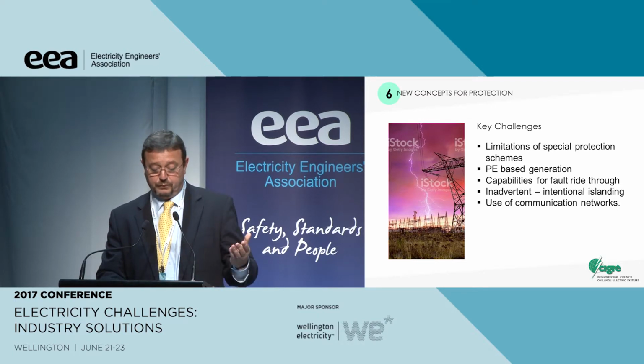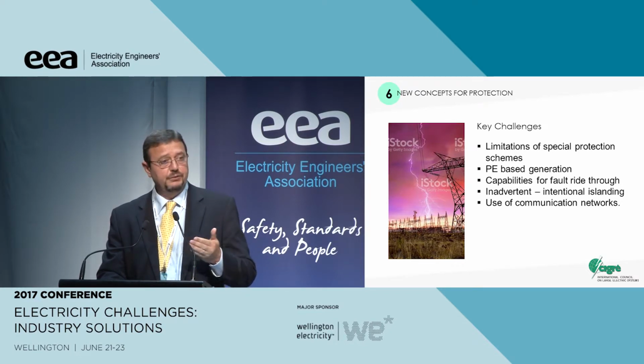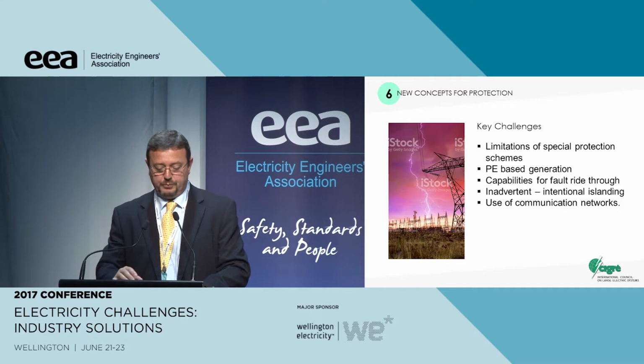Capabilities for fault ride-through, i.e. capabilities of new generators to withstand low voltages due to faults without disconnecting, the coordination between protection and new generation capabilities. The inadvertent islanding detection and intentional islanded operation, i.e. situations when part of the distribution network operates without connection with the higher voltage network as a physical island.